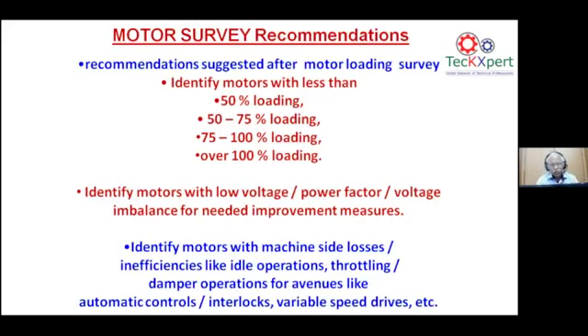On the machine side, we will see what is the idling operation or the throttling operation or the damper operations. These are all the areas to be corrected, and any of the dampers which is used in the machine has to be corrected to a VFD. Instead of a damper, a VFD definitely has a 40% improvement in the energy losses; they can be reduced by almost 40% from a damper to a VFD as such.